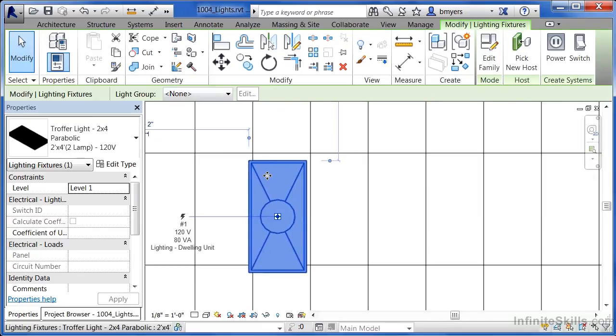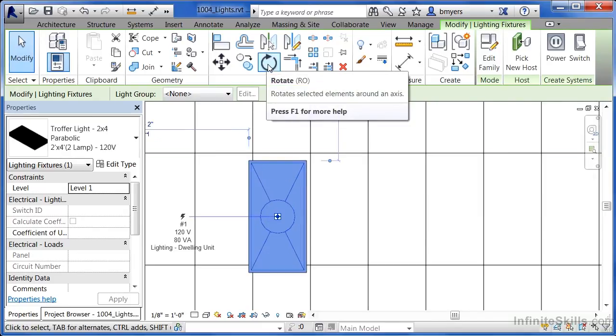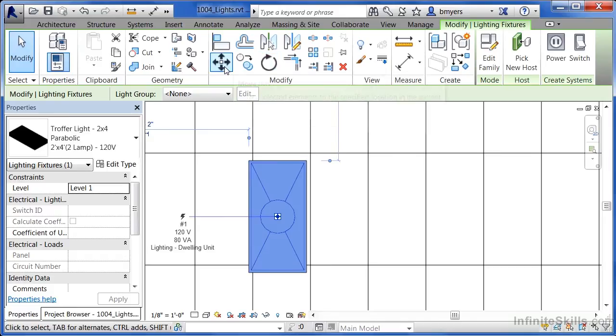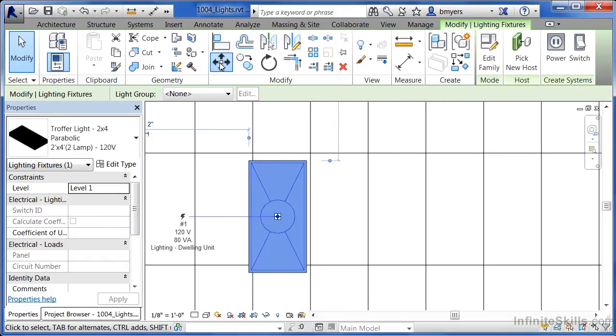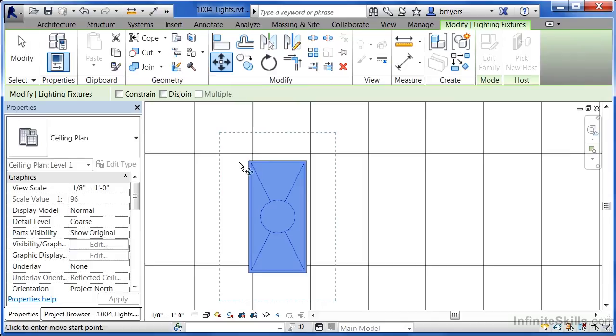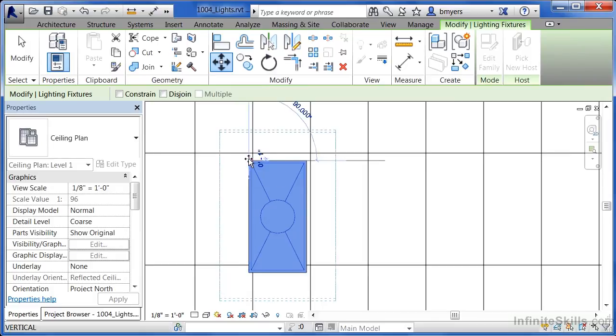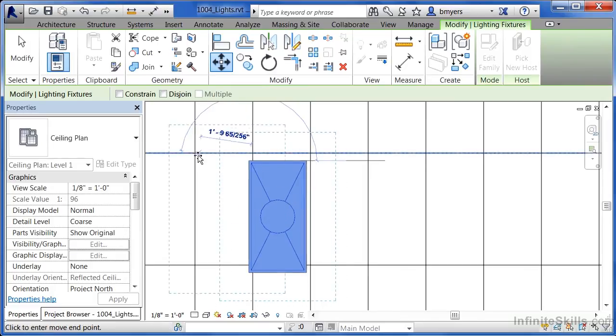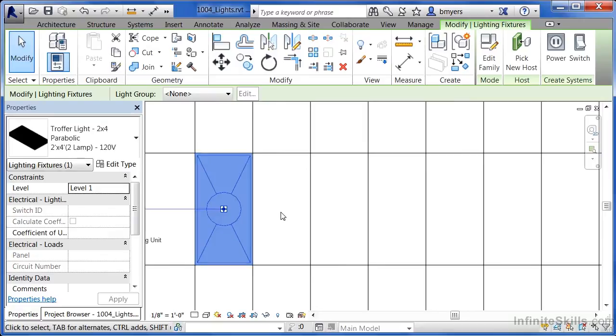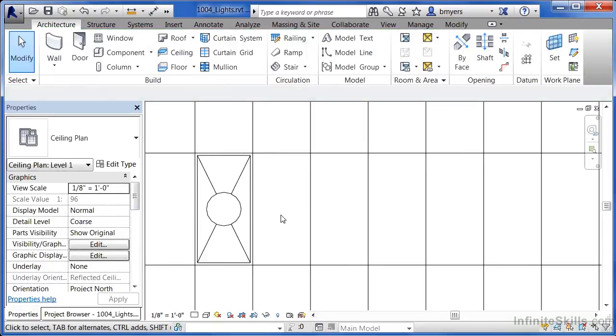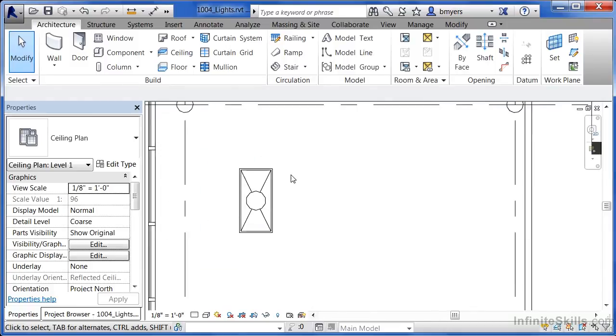Once the light has been highlighted and rotated, come up here and select—not the Rotate command—but the Move command. When you pick Move, you can pick an intersection, in this case the corner of that light fixture. You'll also be able to move over and pick the intersection where those two lines come together. As a result, if you hit Escape a couple times, you'll now have placed that light fixture directly on the ceiling grid where it belongs.